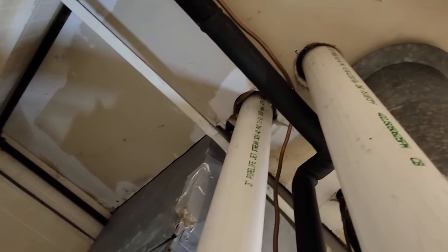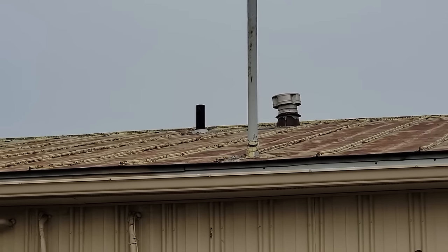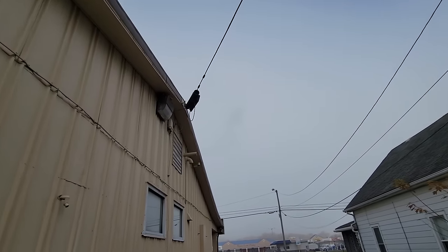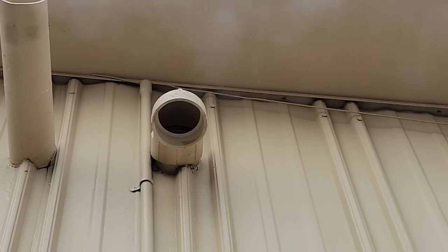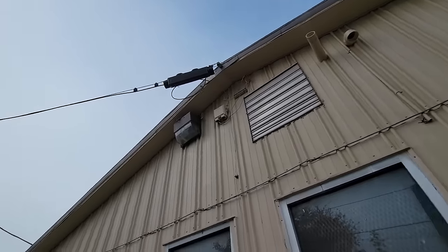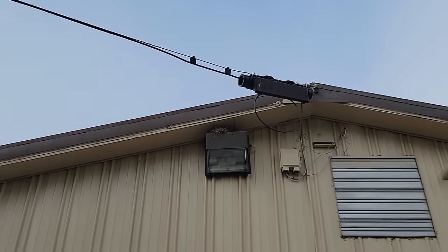That stuff we got there is just remnants of what is probably in there. Let's go and see if we can see something outside. From what I'm seeing here, that looks like the old flue pipe for the old furnace, and that black thing is either a vent for the plumbing or it's the vent for the furnace. There it is. So at least it's 3 inches all the way up and out. There's evidence all over the place - like I always say, you've got to build the case. See that right there? That's the bird's nest. The birds are living here like a bunch of freeloaders.